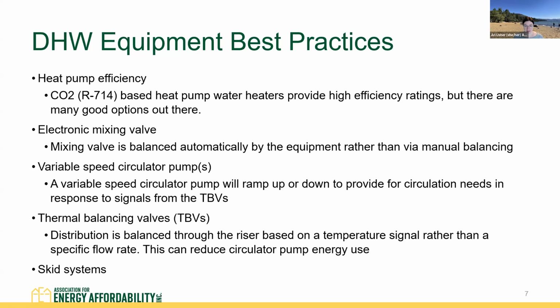In terms of the mixing valve, something to consider is an electronic mixing valve. A thermostatic mixing valve needs to be balanced manually on plant startup, and then also may need to be balanced throughout operations. So an electronic mixing valve will be balanced automatically, and that really takes out some of that extra work with the manual balancing.